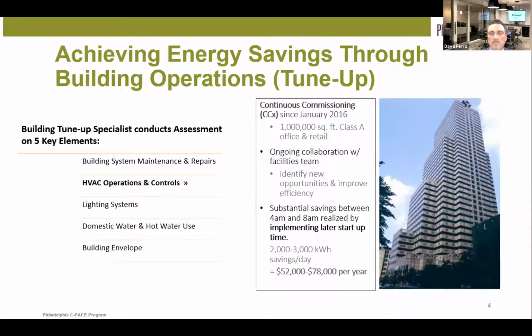This is an example of where continuous commissioning can really help you achieve great savings through minimized costs. Here's a 1 million square foot Class A office and retail facility doing continuous commissioning, so they're in that higher performance situation. They have sophisticated building controls, with set points and real-time monitoring. They install systems to monitor continuously, and they're achieving anywhere from $52,000 to $78,000 in savings per year by managing demand and variable use.